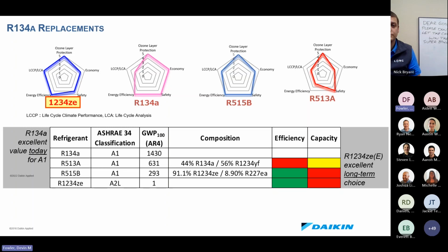When looking at the efficiencies of these refrigerants compared to R134A, R515B is going to have the same, if not better, efficiency than R134A. The only issue there is, like I said, we do take about a 25% capacity reduction. This is something to look at if you're wanting to do a retrofit of an old 134A machine. Depending on your size, R515B may not be the best option for you. You might want to look at R513A in order to keep that same capacity on your machines.